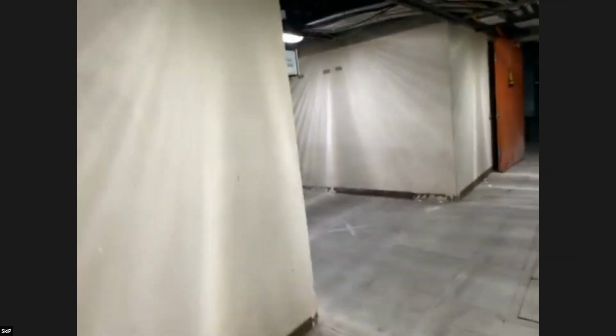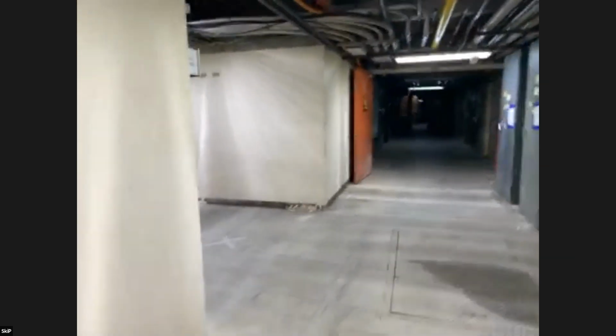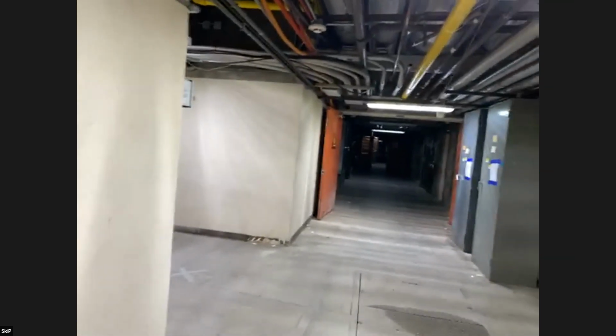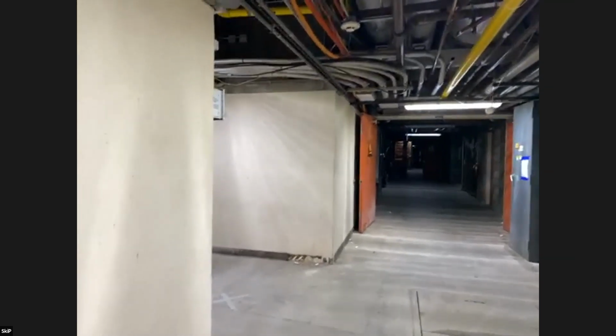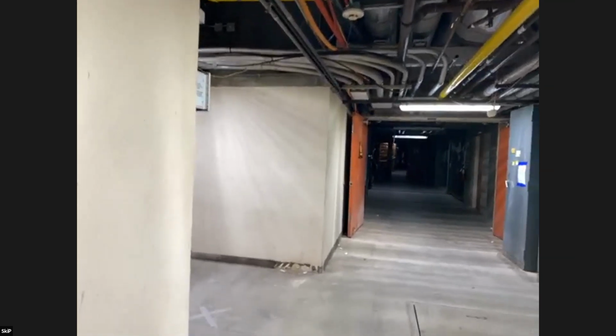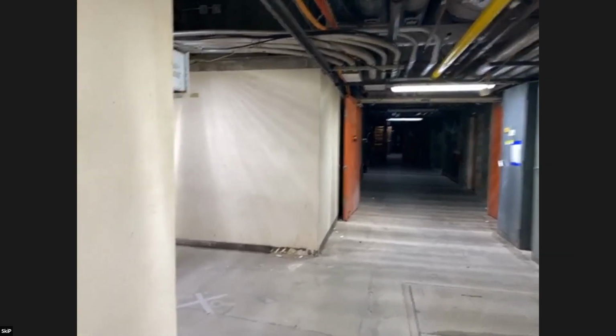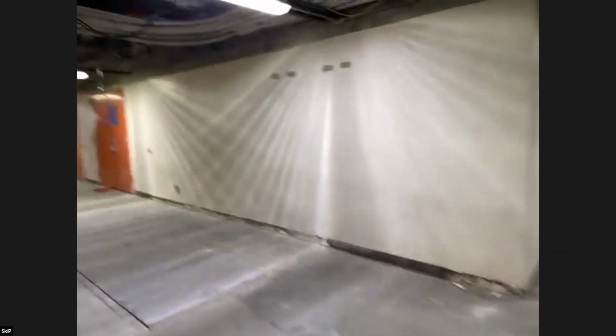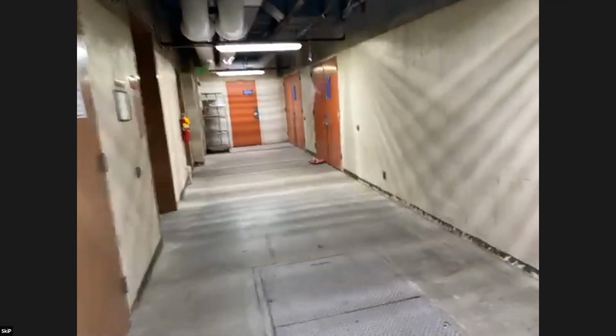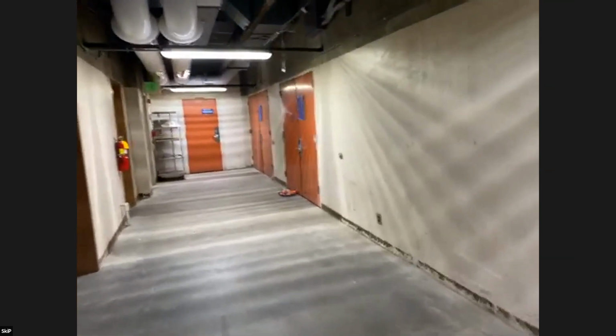On a science building, because of the experiments and stuff, if it's a 90-degree day outside, we have to take that 90-degree air, cool it down to 55 degrees, blow it into the classroom, and then just exhaust it out the top of the building. So we're not able to recirculate and use that energy; we have to use maximum energy for everything we do, 24/7. Science buildings are super inefficient, and we do what we can to make them more efficient.